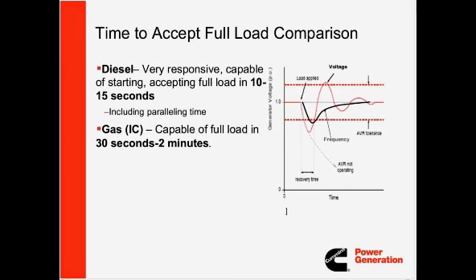So if we talk more about the transient performance of the generators, diesel, because of its high torque capabilities, is very responsive and is capable of starting and accepting full load in 10 to 15 seconds. This is required by many emergency standards, such as the National Fire Protection Association NFPA 110 standards for standby and emergency loads for level 1 systems. For those life safety and critical loads, you need to recover from a voltage drop and a frequency drop within 10 seconds from the moment of power interruption. And this also applies to many legally required loads, such as those used in public facilities.